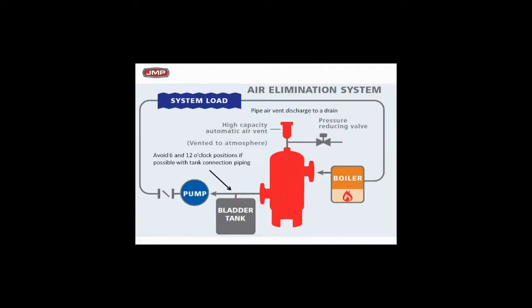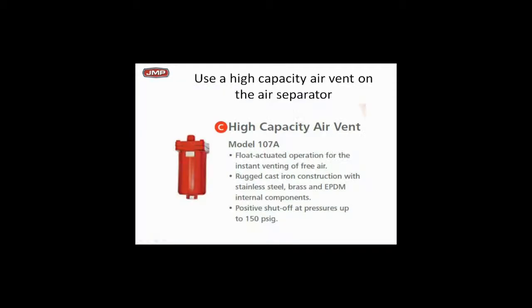Pipe the air vent discharge to drain. The vent from that should go to drain to get it down the drain so you don't get a wet floor if it starts leaking a little bit. Here's a picture of that — the float actuator, high-capacity air vents, heavy duty, rugged cast iron. You want to pipe these things to a drain somewhere in case you get a little water coming out with the air.